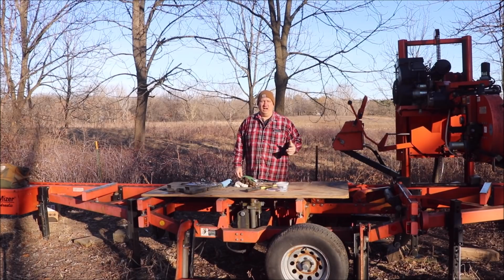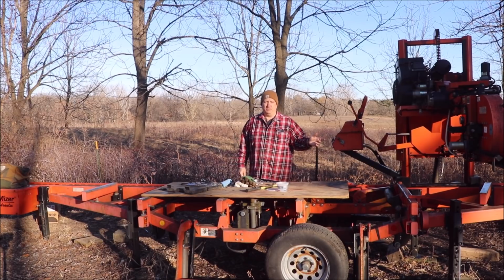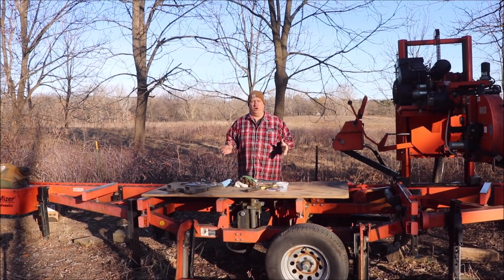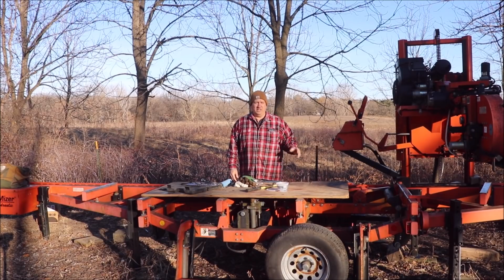That's a quick video on repairing the power feed, and for any of you guys that have these mills that are having similar problems with diagnostic problems, don't be afraid to call Woodmizer. Those guys are fantastic over there. They'll take all the time you need, and then they'll literally walk you through the process of troubleshooting it. They were fantastic with me, so highly recommend it. If you're having a problem, give them a call.